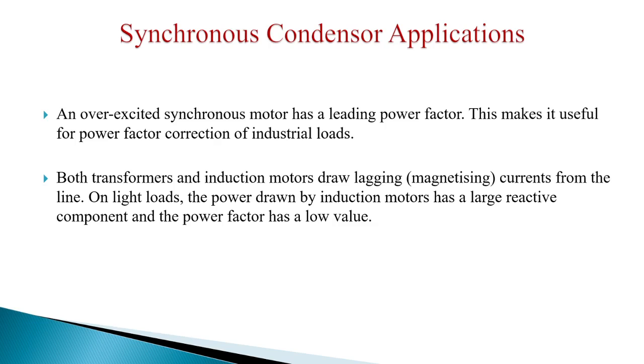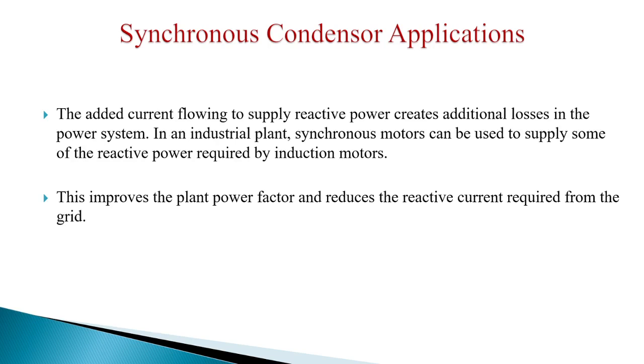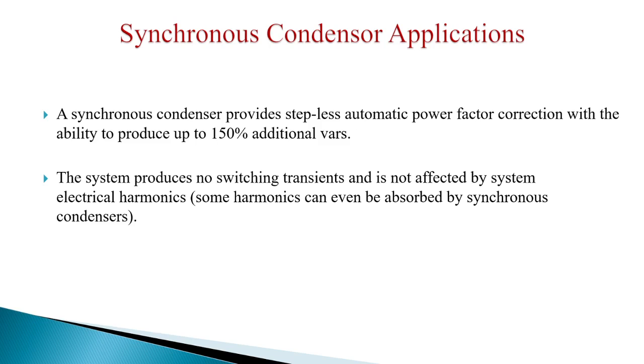An over-excited synchronous motor has a leading power factor. This makes it useful for power factor correction of industrial loads. Transformers and induction motors will draw lagging currents from the line. A synchronous condenser will provide stepless automatic power factor correction with the ability to produce up to 150% additional volt ampere reactives.